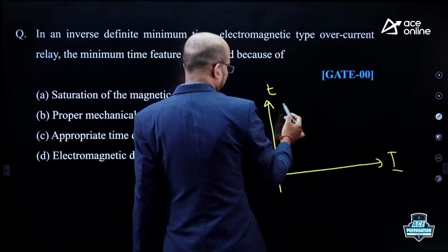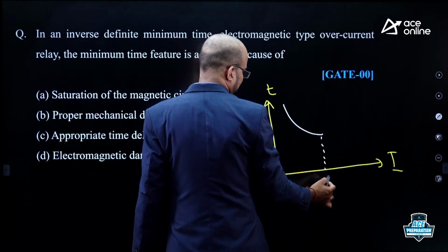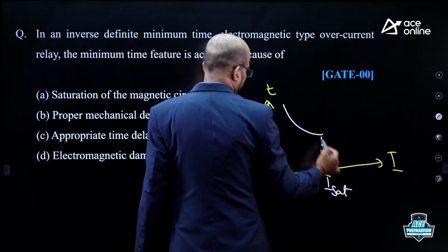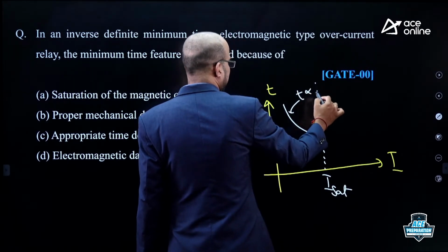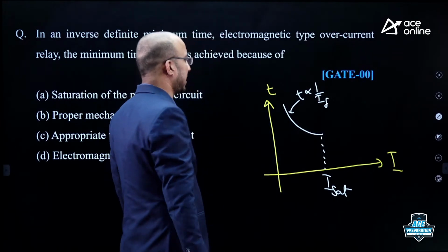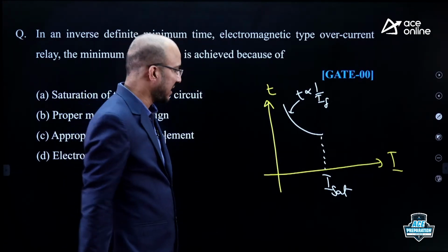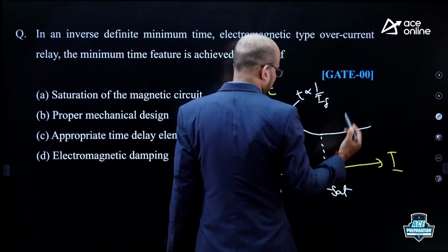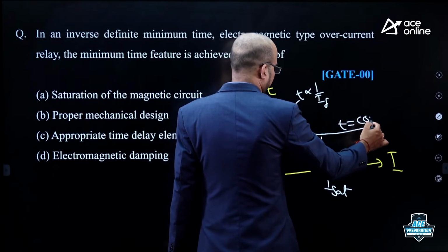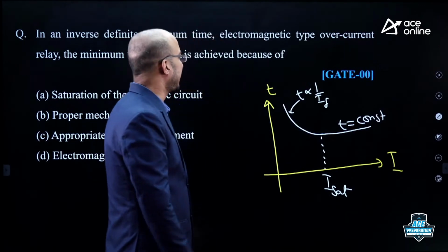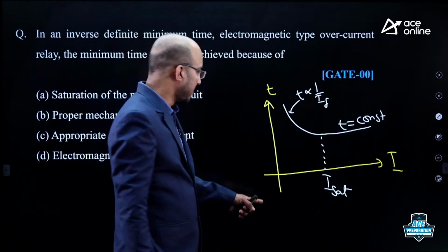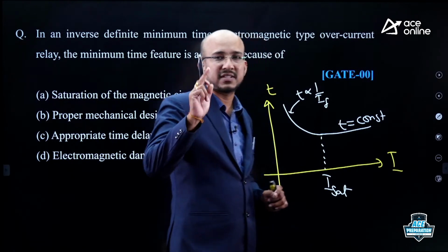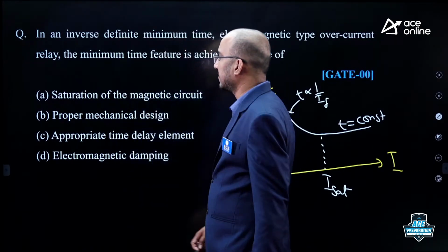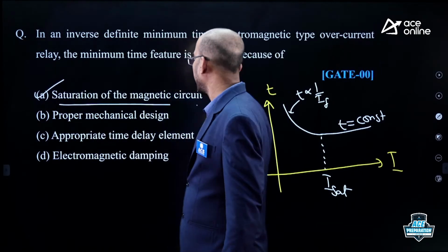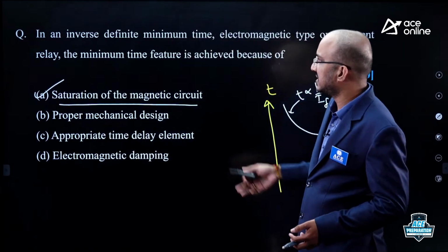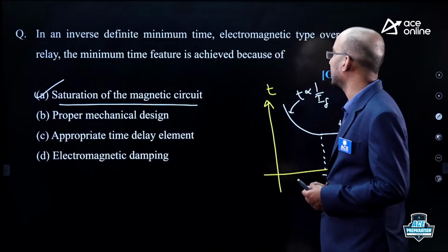So in case of IDMT, up to the saturation point you will get an inverse characteristic. Time of operation is inversely proportional to fault current. Beyond saturation, time of operation is constant, so it is becoming definite here. So how is the definite time characteristic achieved here? By considering the concept of saturation of CT core. Okay, that is nothing but the saturation of the magnetic circuit is the basis for the inverse definite minimum time relay.